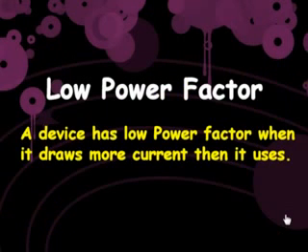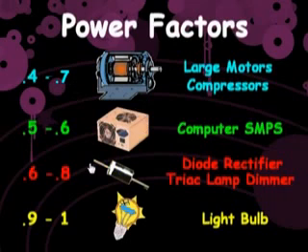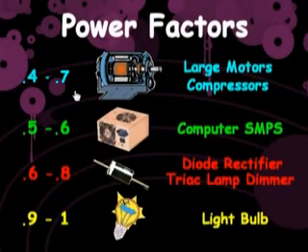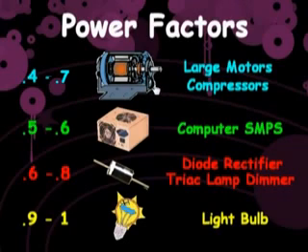A device has low power factor when it draws more current than it uses. A power factor of 0.7 means that 70% of the amps flowing in the electrical wires produce watts that turn this motor's rotor, while 30% of the amps flowing are reactive amps that produce no watts.